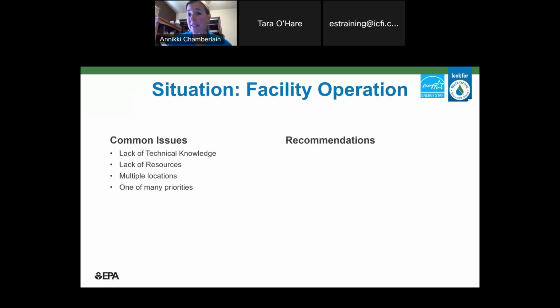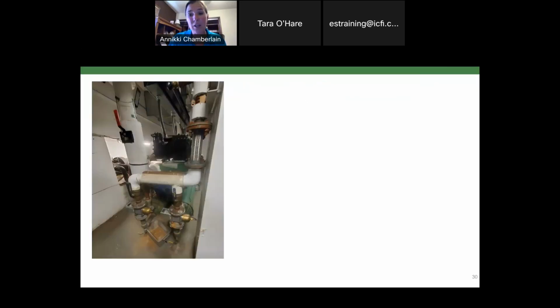Okay, now we have facility operations where the facility person is running the tower and not the service provider. So a lot of times here people are like, oh, you're a mechanic, you can run the tower. That usually doesn't work very well. Typically lack of technical knowledge, lack of resources, like do you have resources to chemicals, to sensors? A lot of times these people have multiple locations or a lot of priorities. So here's a good example. This is a pump and dump, so it just has a chiller, not a cooling tower, but is a good example. These valves here often fail.